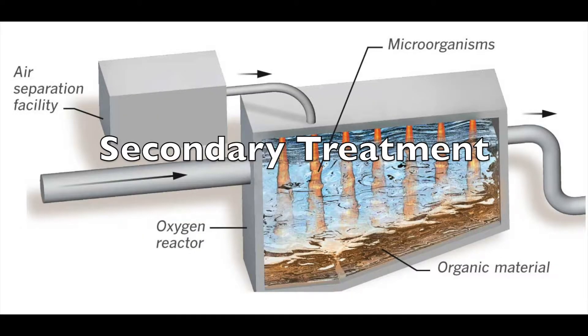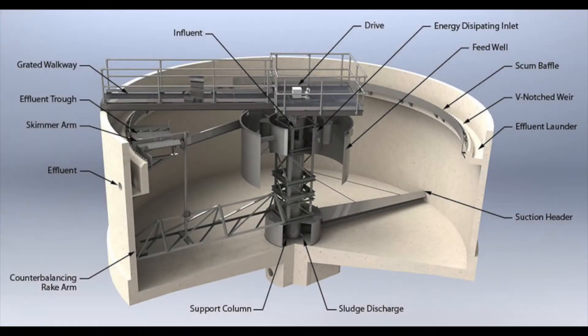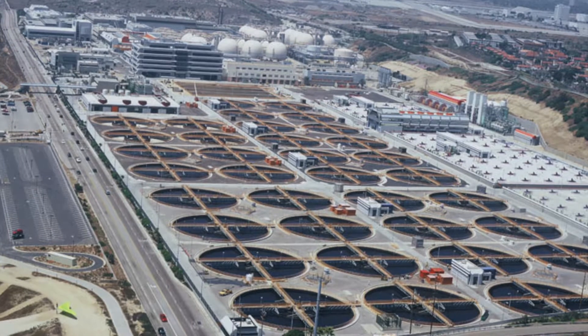At this oxygen-abundant secondary treatment system, bacteria consume most of the solids and eventually sink to the bottom, where they are sent to the clarifiers. Next, at a cryogenic air separation facility operating at negative 196 degrees Celsius, 250 tons of liquid oxygen are sent back to the previous tank to aid in bacteria growth.